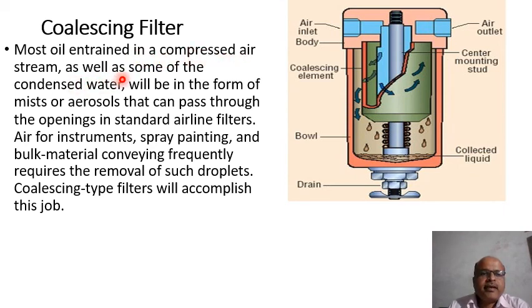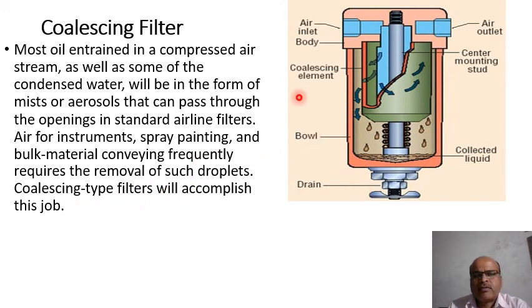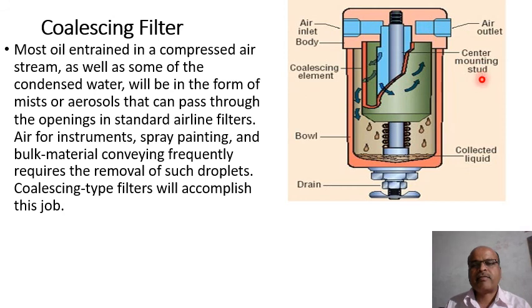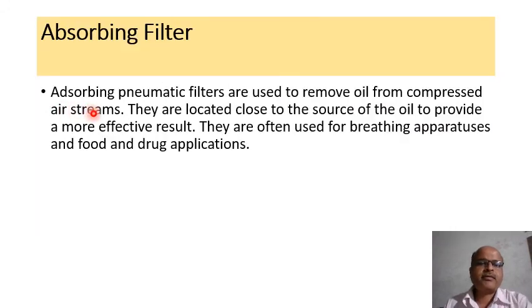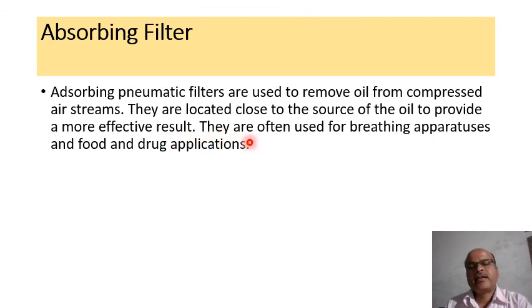Most oil and water entrained in a compressed air stream, as well as some condensed water, will be in the form of mist or aerosols that can pass through the openings in standard airline filters. Air for instruments, spray painting, and bulk material conveying frequently requires the removal of such droplets; a coalescing type filter will accomplish this job. The coalescing filter comprises: air inlet, body, coalescing element, center mounting, collected liquid, and drain. Adsorbing pneumatic filters are used to remove oil from compressed air streams, located close to the source of oil, and are often used for breathing apparatus and food and drug applications.